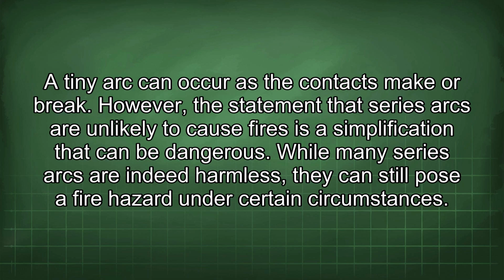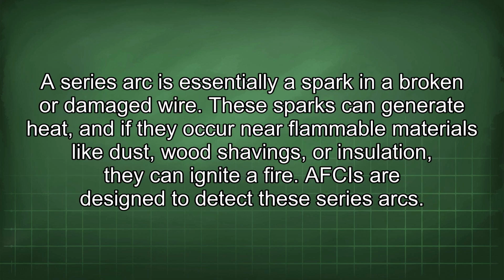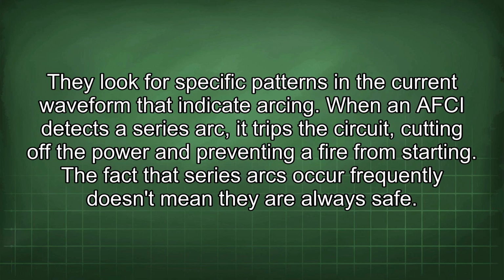While many series arcs are indeed harmless, they can still pose a fire hazard under certain circumstances. A series arc is essentially a spark in a broken or damaged wire. These sparks can generate heat, and if they occur near flammable materials like dust, wood shavings, or insulation, they can ignite a fire. AFCIs are designed to detect these series arcs. They look for specific patterns in the current waveform that indicate arcing.